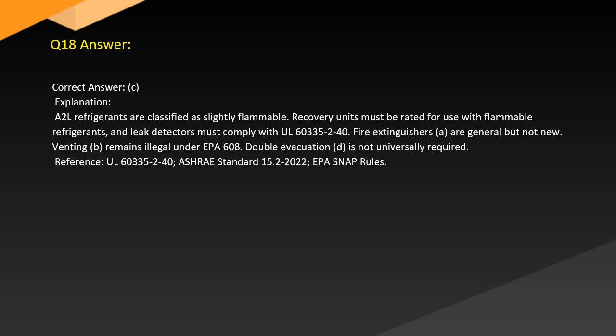Answer. Correct answer: C. Explanation. A2L refrigerants are classified as slightly flammable. Recovery units must be rated for use with flammable refrigerants, and leak detectors must comply with UL 60335-2-40. Fire extinguishers are general but not new. Venting (B) remains illegal under EPA 608. Double evacuation (D) is not universally required. Reference: UL 60335-2-40, ASHRAE Standard 15.2 2022, EPA SNAP rules.